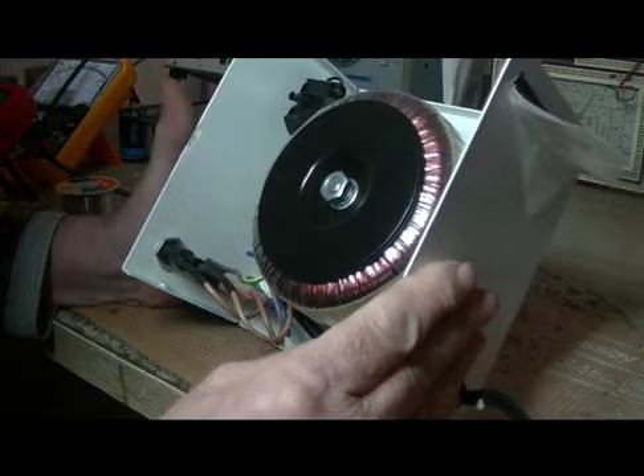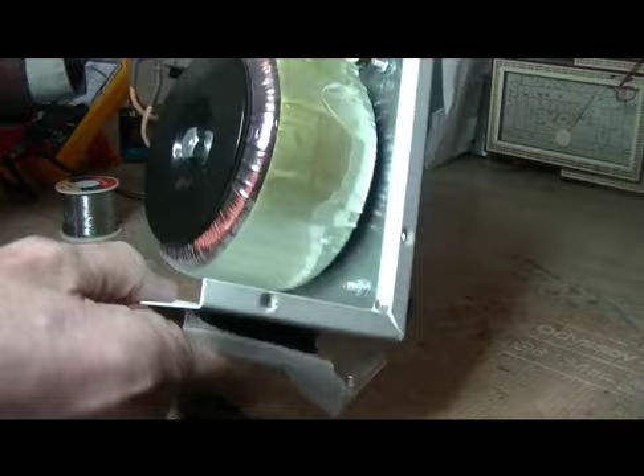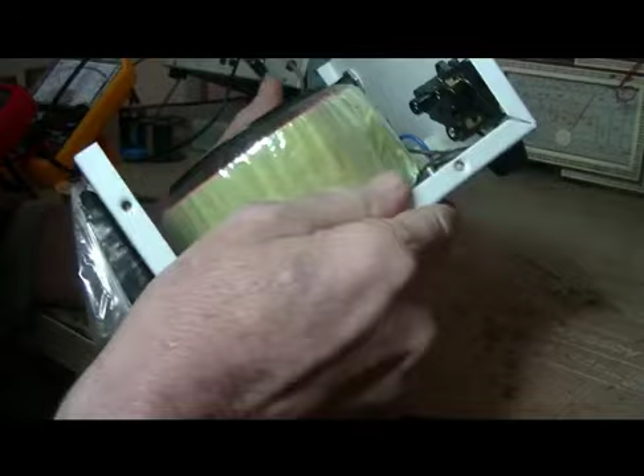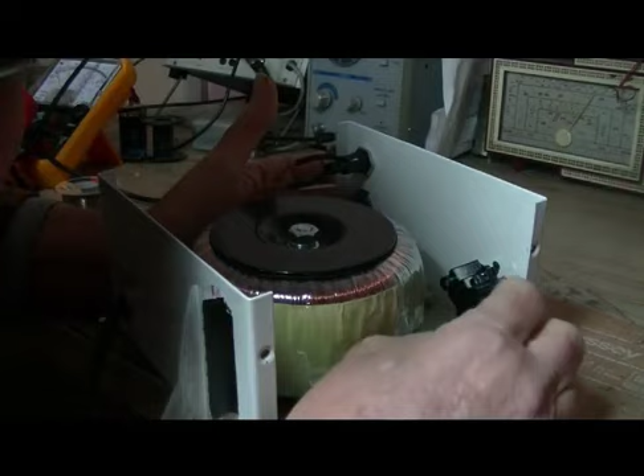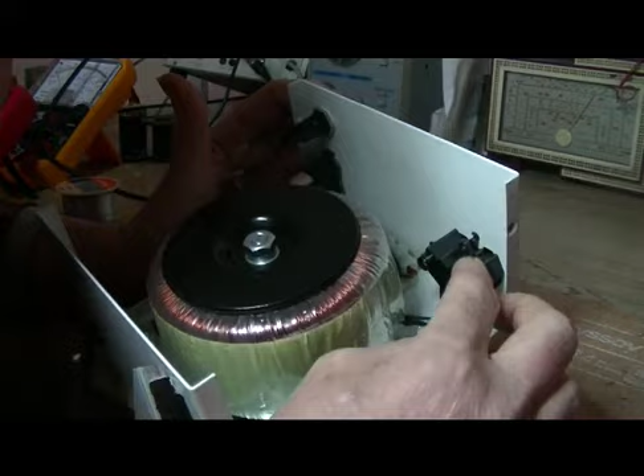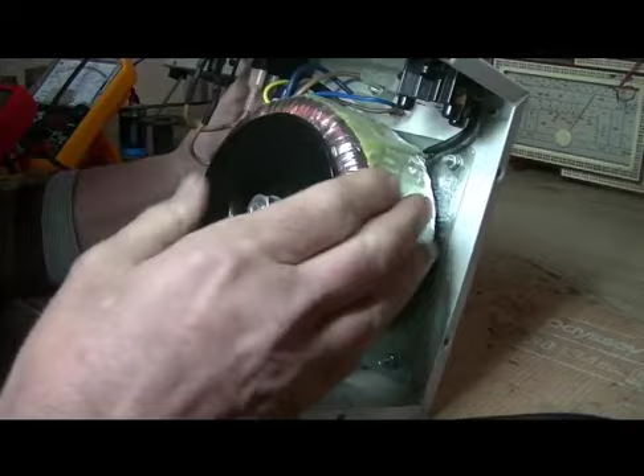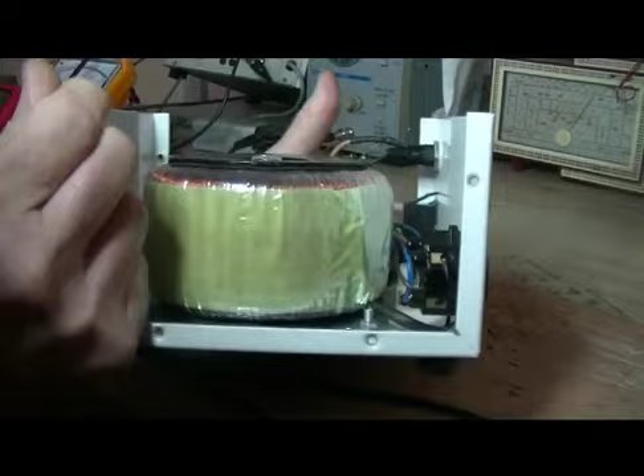What have we got here? Okay, fuse, on-off switch, input. Earth is tied to ground. But let's look at the output here. Here's our plug, and yeah, two black wires going active and neutral, coming directly from the secondary side of the transformer. So there's no earth connection, and I can physically see that. This thing is definitely isolated.